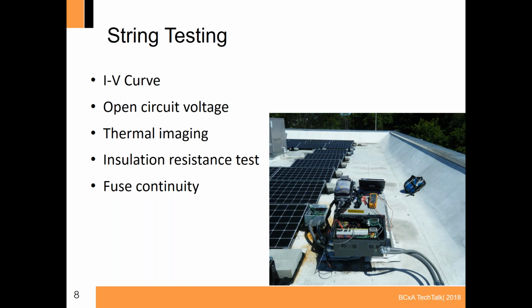Thermal imaging, the next one down there, is a really excellent tool, as I'm sure all of you know outside the world of solar. These thermal imaging cameras are really great when it comes to almost any type of commissioning. The same holds true for solar PV commissioning, but really it can be used to see hot spots on the array. On the modules, we can see if modules are operating properly or not. Electricians, we love thermal imaging cameras for our conductors, for our fuses or circuit breakers to see if they're running hot. Our terminals, if the terminals are running hot, again, it's not something we want to just go stick our bare hands on, but we can safely evaluate that through these thermal imaging cameras. Identify a hot spot, and typically that's a good sign that there's an issue. So it's a nice, safe, accurate way to determine if there's an issue.